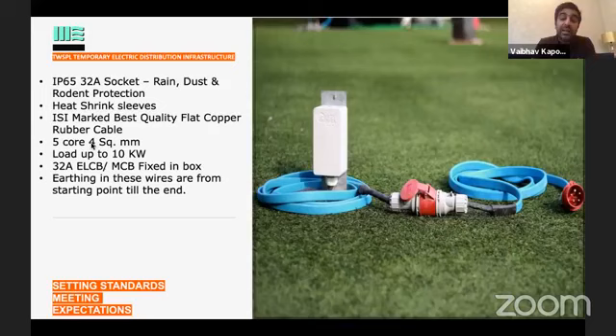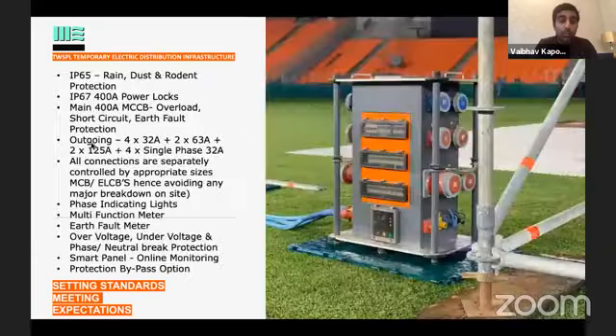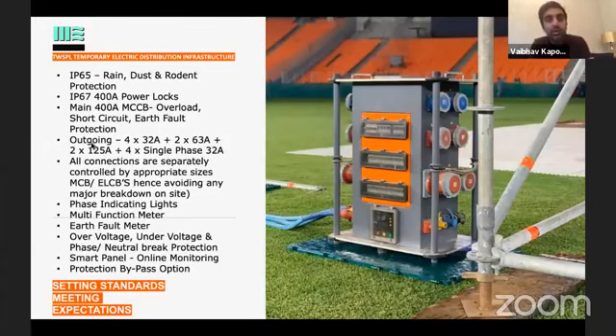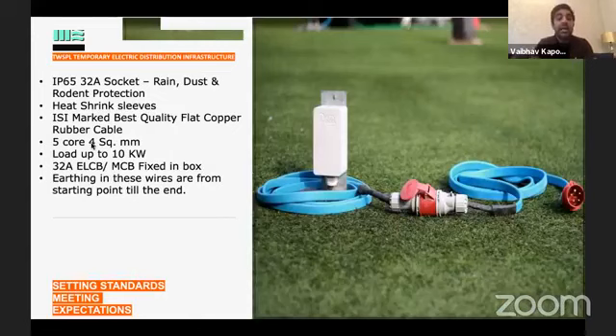So everything remains the same. Over in this picture, the socket size is 32 amps. The wire size is 5-core 4, which can again take a load of 32 amps. And inside this box, there is also a 32 amp MCB. If I break any chain in between, starting from the 32 amp socket, 32 amp suitable cable, and 32 amp MCB, everything we've spoken about overload applies.